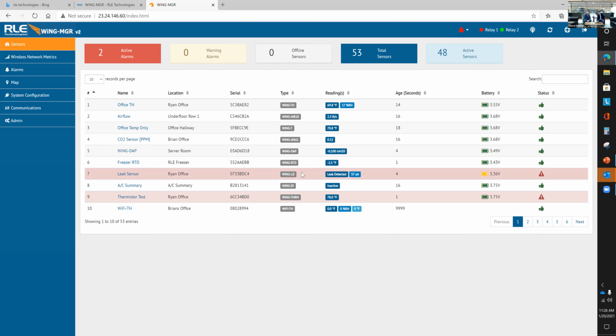The almighty feature a lot of people are looking for is wireless leak detection. So we kind of stopped this, and this is why it looks like this, kind of red - and actually this is a good indication. You can see it's still communicating with the age of data, but we stopped this to show that you can actually get a value of how wet the cable is. In some environments where I've installed wireless leak detection, we've adjusted parameters to make sure that condensation or some other environmental factor forcing humidity onto the cable is avoided. The goal is to minimize false alarms and get you to pay attention to the alarm if it shows up. Hopefully it doesn't, but I think everybody on the call has probably heard or experienced a leak at least once, which has caused a lot of problems and cost.